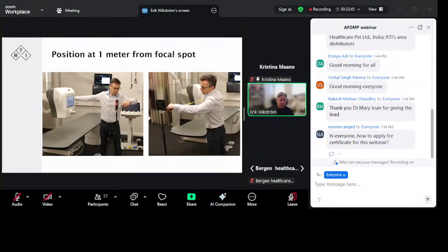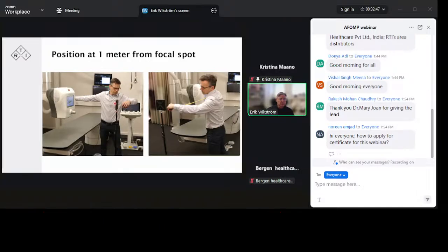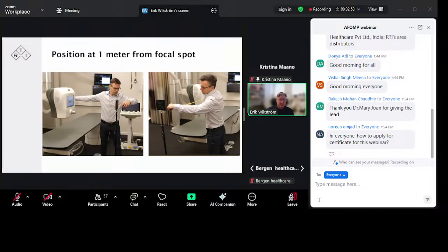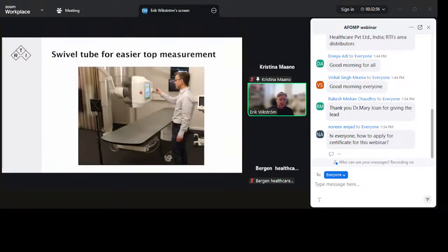Here's our probe, the scatter probe, whichever probe you're using, positioning at 1 meter from the focal spot. That's what we need to try to achieve. Measuring from the top may be a bit tricky, but in many cases you can swivel the tube so that you can then, in that way, measure the leakage out of the top of the X-ray tube.